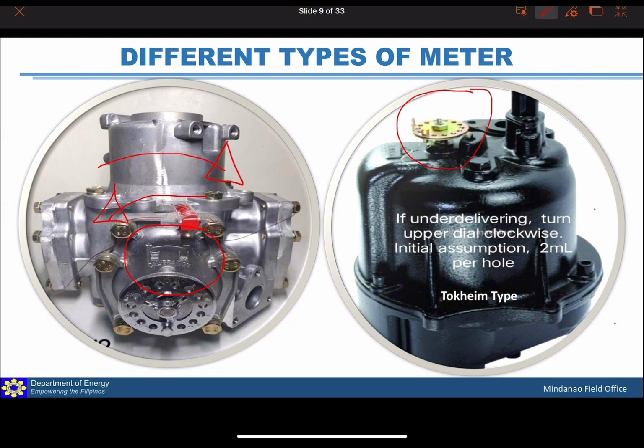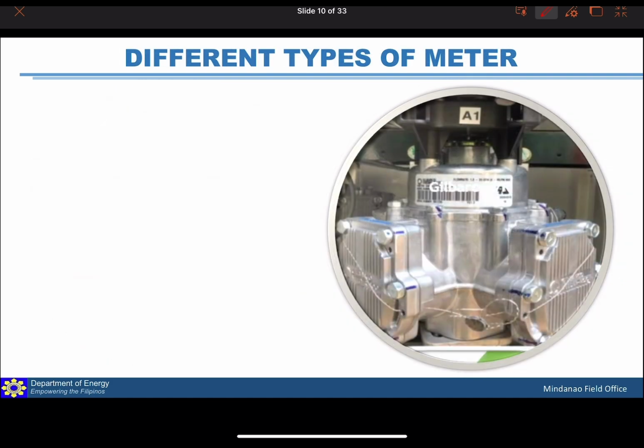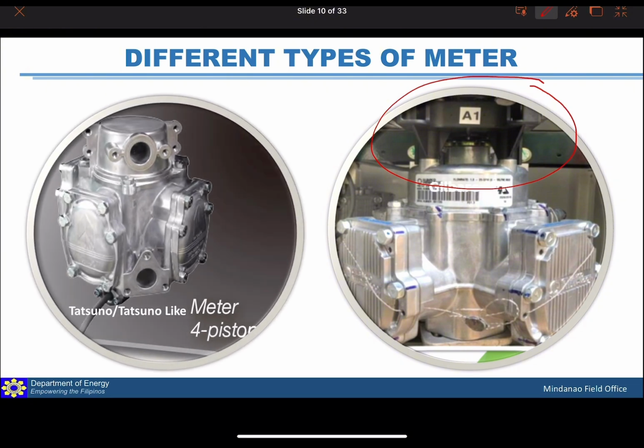But based on experience sa field, not all the times na tama yung naka-engrave here sa meter. So we need to do trial and error if you found during inspection na magkaiba yung ginagawa niya based sa pag-dispense natin sa calibrating bucket over the engraved na instructions sa meter. Next is a Gilbarco. So Gilbarco is electronic, but there's a knob in the upper part that is being adjusted, being turned into calibration mode. Tapos ina-adjust na siya through keypad. Then for Tatsuno or Tatsuno-like, wala kayong makikita ng mga holes on the side because this is purely electronic.